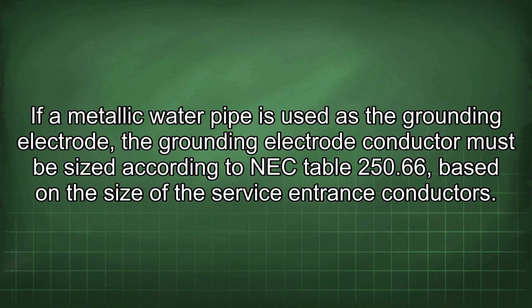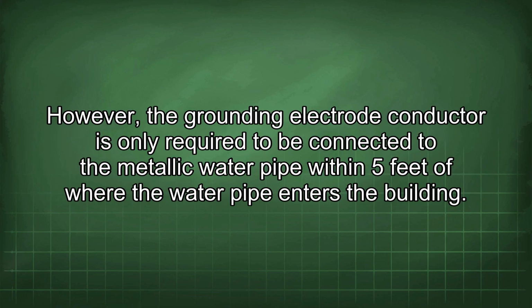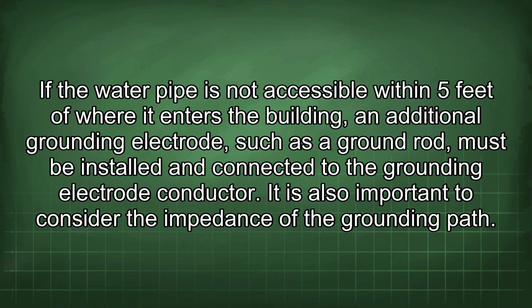If a metallic water pipe is used as the grounding electrode, the grounding electrode conductor must be sized according to NEC Table 250.66, based on the size of the service entrance conductors. However, the grounding electrode conductor is only required to be connected to the metallic water pipe within 5 feet of where the water pipe enters the building. If the water pipe is not accessible within 5 feet of where it enters the building, an additional grounding electrode, such as a ground rod, must be installed and connected to the grounding electrode conductor.